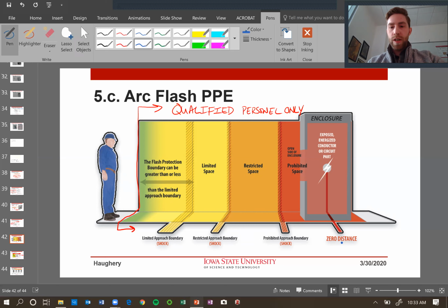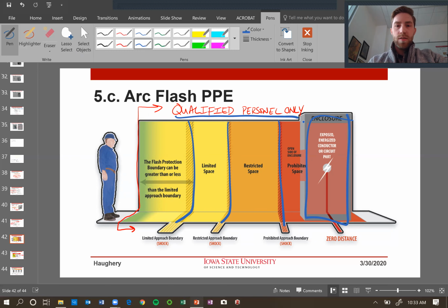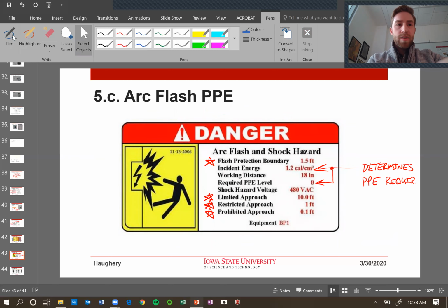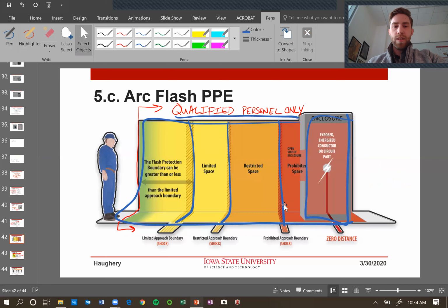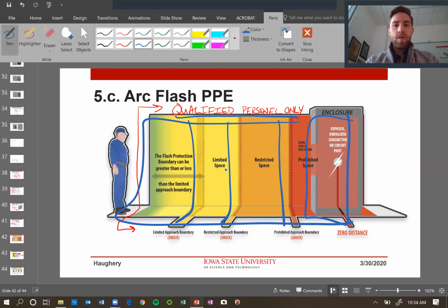And really what this graph is showing is we have our enclosure here where I have my switch and it has that arcing happening, and there are different zones that you can and can't be in, and really qualified individuals are the only ones inside this large zone area. But then as you get closer and closer, the level of PPE increases. And so if we look at that, that's defined by the flash boundary, right? There's a distance, and also the incident energy. How much energy capability does that piece of equipment have if it arcs? And so then we have these approach boundaries: limited approach, restricted approach, and prohibited approach, which correlate to all of these zones here.